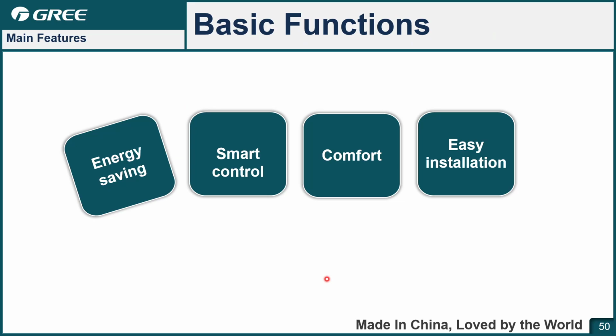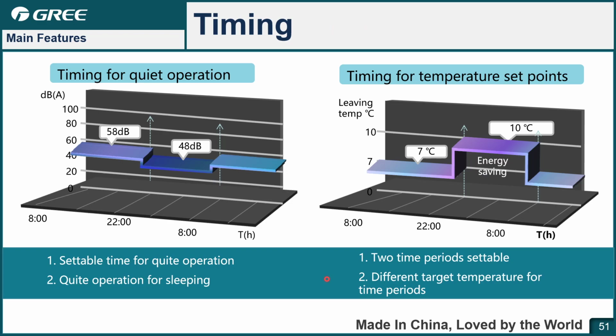And for basic functions, first one, timing. For VERSATI 3, you can choose the timing for quiet operation. If you choose quiet timing during the night, the unit will start quiet running to reduce the noise by around 10 decibels. Also at night, the load demand is lower than in the daytime. So this is a choice for customers who want to balance use and sleeping; they can choose the timing for quiet operation during the night.